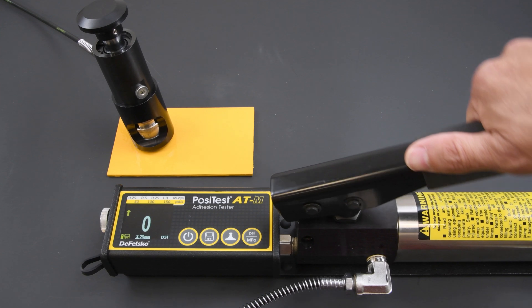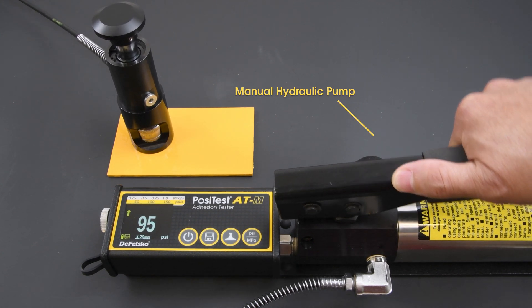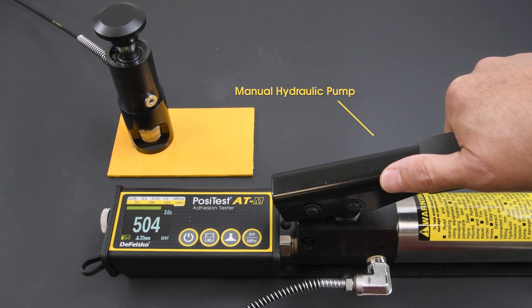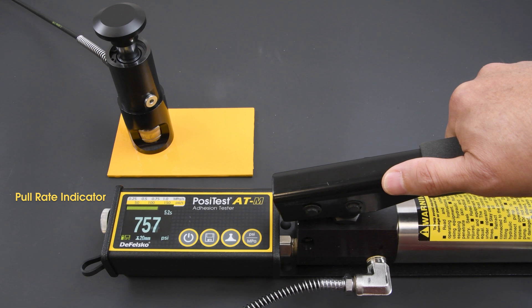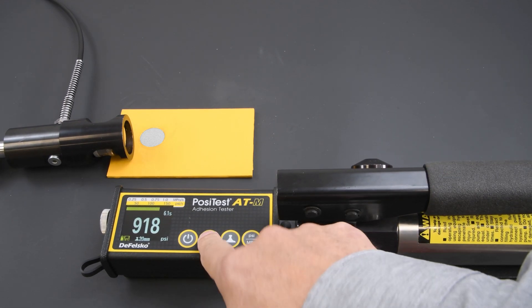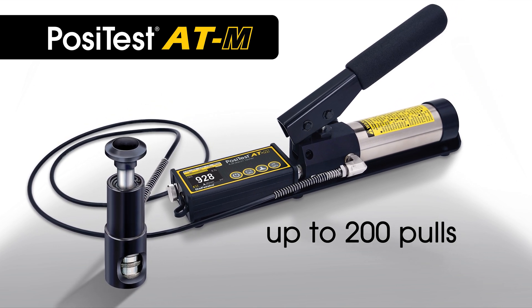The PosiTest AT-M manual adhesion tester features a manual hydraulic pump designed to apply smooth and continuous pressure with a single stroke, a pull rate indicator to manually monitor and adjust the rate of pull, and an internal memory that stores all the data of a pull-off test for up to 200 pulls.